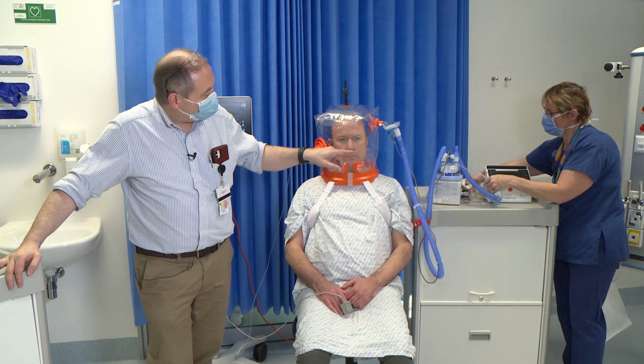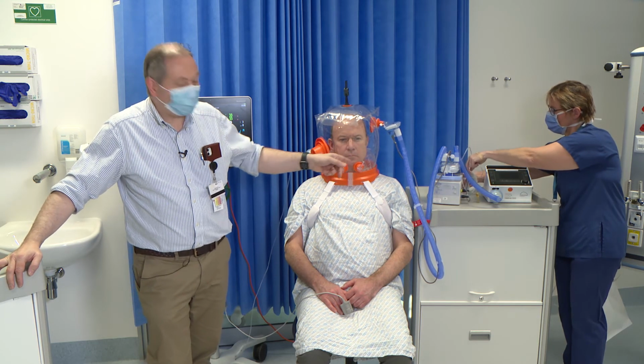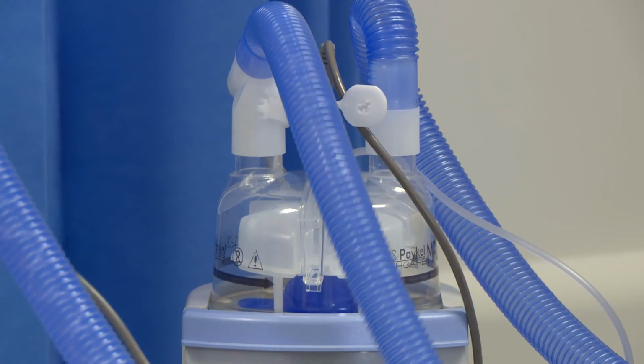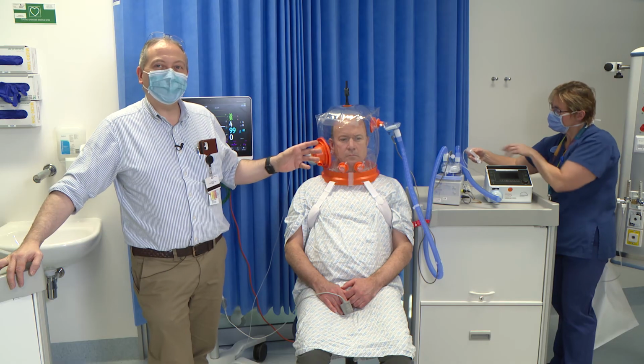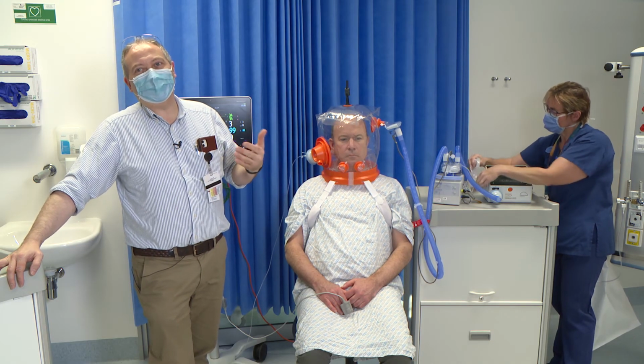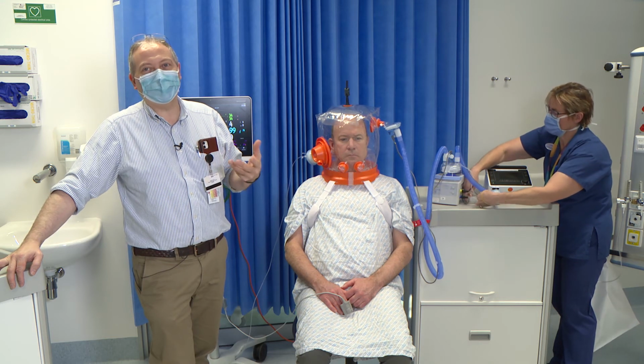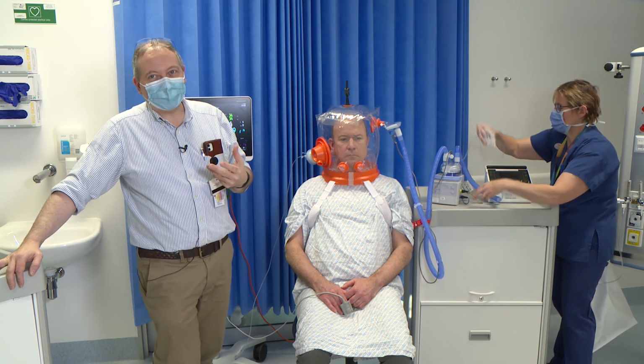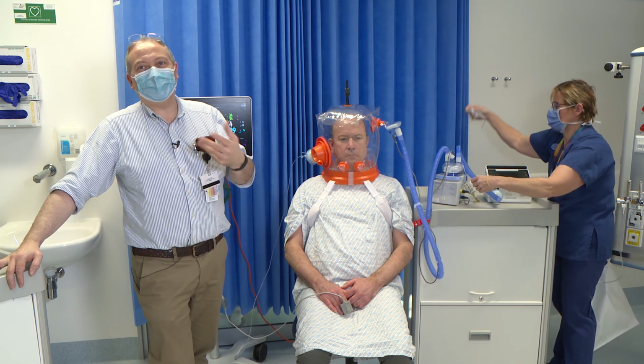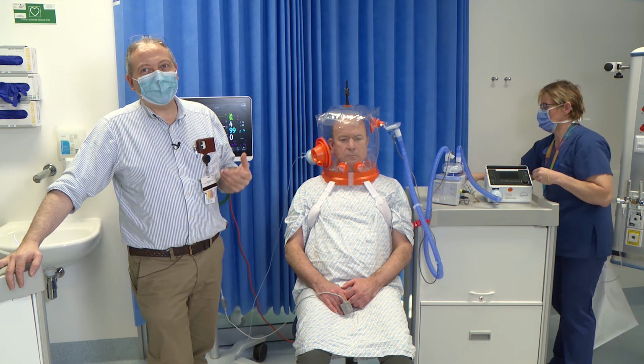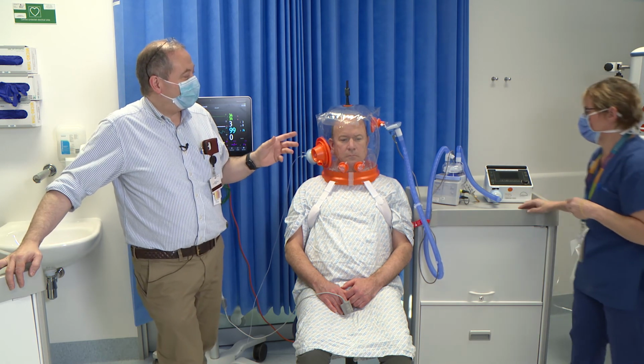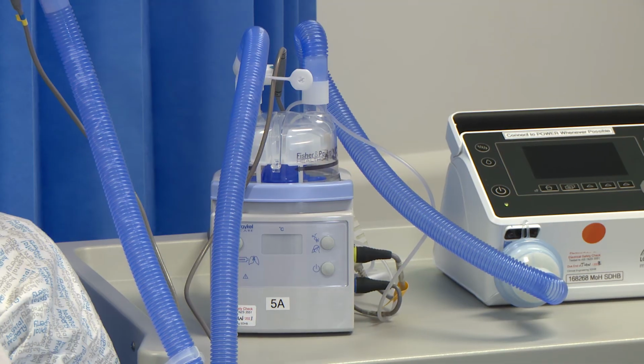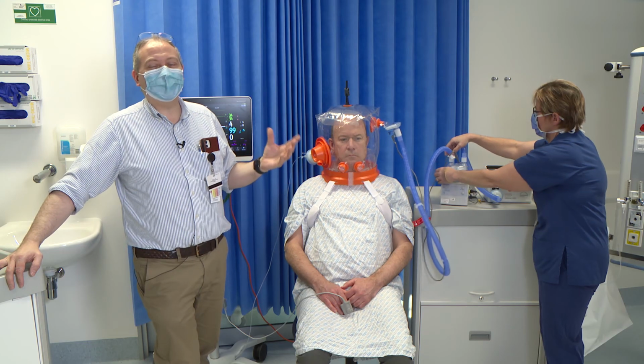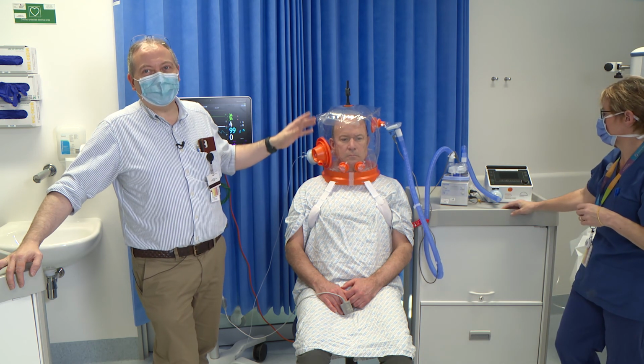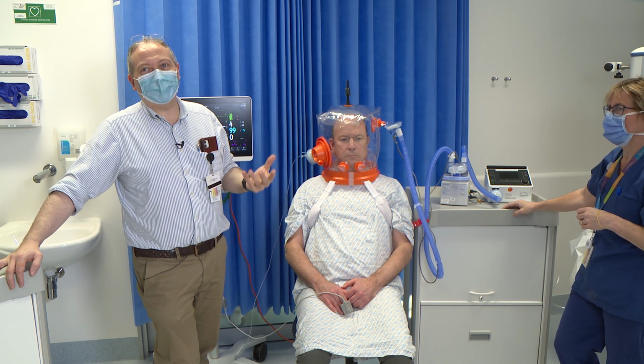You'll notice that we have got our home CPAP machine attached through a humidifier. At the moment we don't have the humidifier on, and it's not absolutely essential because the home CPAP machine is just compressing room air, which is already humidified at the ambient temperature and pressure for the environment we're in. However, because of the high gas flows, there is still a risk of ciliary drying in the lungs, and so we do recommend that you use the humidifier, and it's even more important to do that if you've added oxygen, because compressed oxygen is a dried gas. And so the humidity of the gas in the helmet will drop markedly the more oxygen you're adding to it.